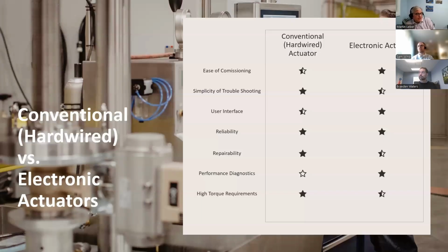Performing diagnostics—again, it's not that easy. Yes, the electronic actuator will tell you its faults. There are none of those performance diagnostics on the conventional electric type, but you can get options on the electronic ones where you can actually see a history of the torque of the valve. And when it comes to heavy loads and high torque requirements, the SMB and L120 win out in the end, because they go up to thousands and thousands of foot-pounds of torque output. If you couple that to a gearbox, you can be turning essentially the globe—they get very, very large.